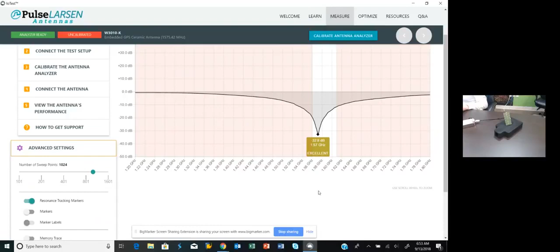And this time I do want to click on advanced settings. These advanced settings allow you to see a bit more on your software use than just what's immediately obvious. You'll note first maybe that the measure section doesn't include automatically the resonance memory trace that was there before. You'll see that the shaded gray area is all just the antenna response. There's not a memory trace to compare with the evaluation board's expected performance. You can select to turn that on here, and now you can see that memory trace saved.